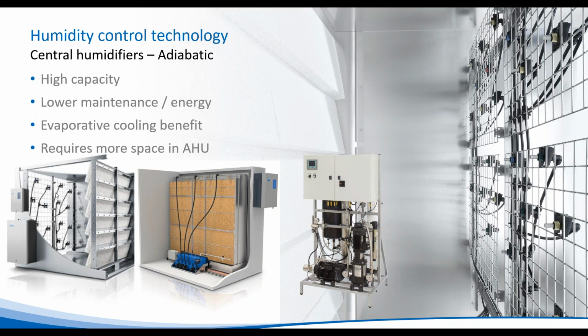And that will evaporate in this section of duct or air handling units. And then any water droplets that haven't evaporated get caught on a ceramic matrix, which then evaporates those water droplets off into the air. So it's a very efficient use of water, and it's a nice hygienic situation. But also by modulating the number of nozzles that are spraying at any one time, we get very close control. So plus or minus 2% RH control. So it's very much horses for courses.